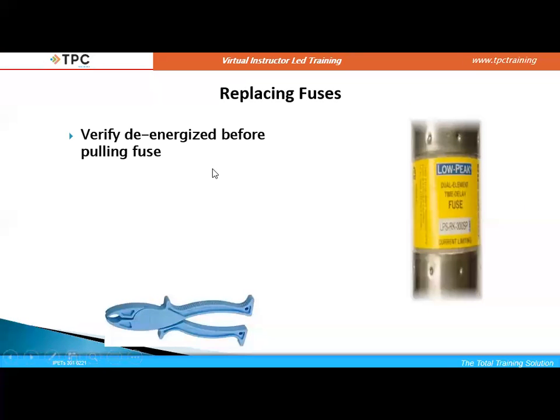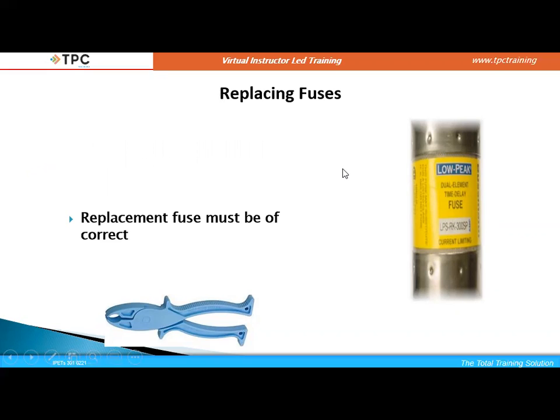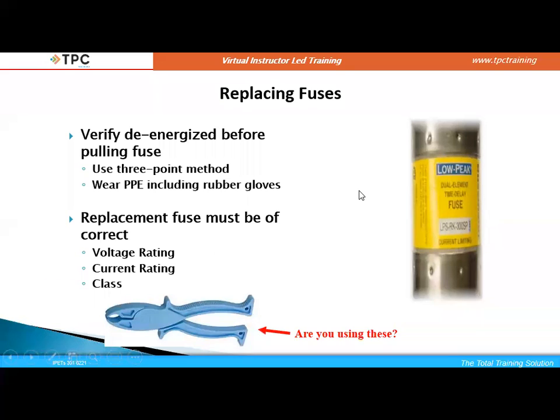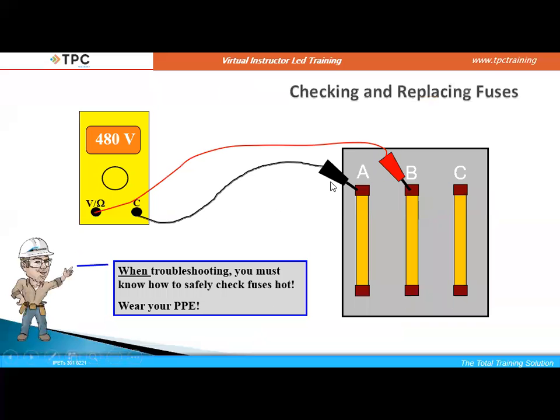Of course, if I am going to replace it, make sure I am de-energized. The only fuses I could replace energized would be something below 50 volts, maybe some control fuses for my control circuits, if there was no other voltage present in that cabinet above 50 volts. And do live, dead, live, wear my PPE, and get that fuse replaced. Make sure it is the exact same one. The voltage rating is the same, the current rating is the same, the interrupting rating is the same, and the same class. So important when we replace them.